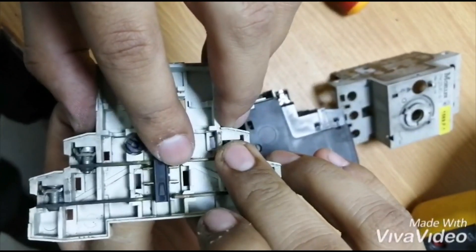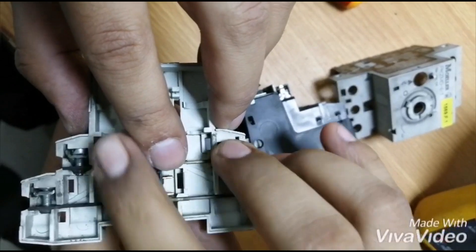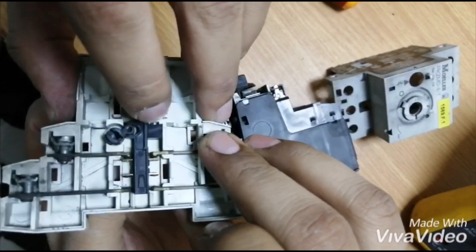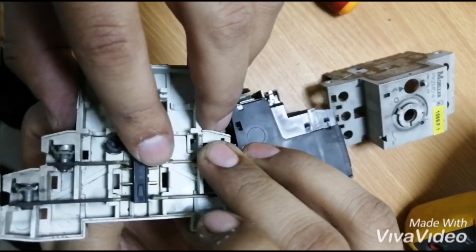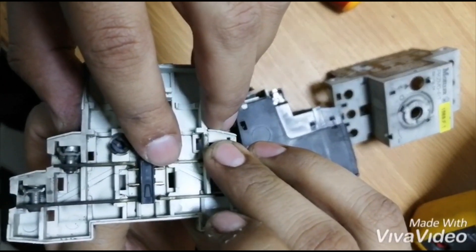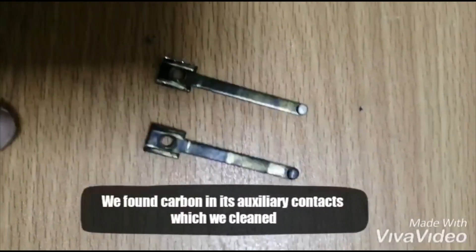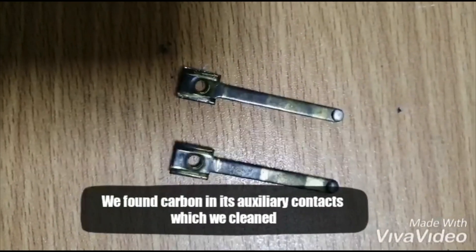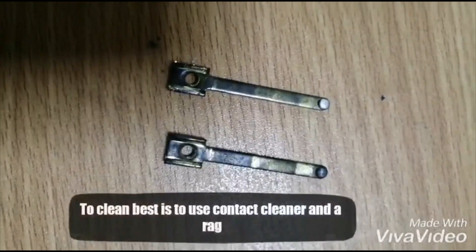I have to put a finger in the middle because without it the spring flings up easily. But we can see it's very simple. And here is the culprit of the video — the contacts of the auxiliary were carbonized. On the top you can see that we have cleaned it, and on the bottom it's still carbonized. Cleaning is not so difficult; you can use a contact cleaner and a rag or emery paper to remove it.